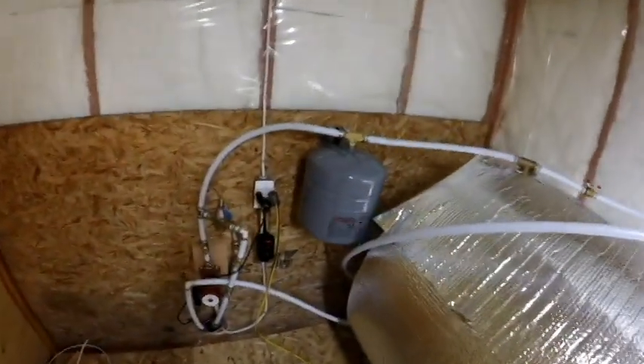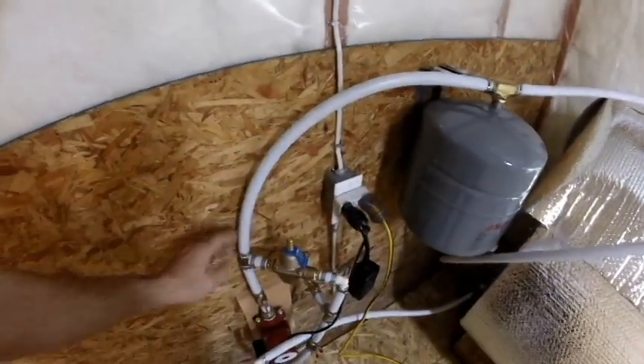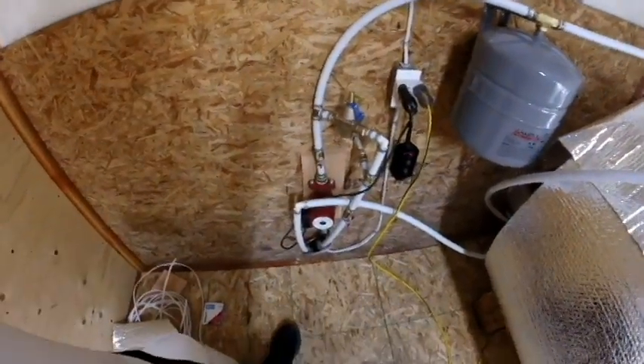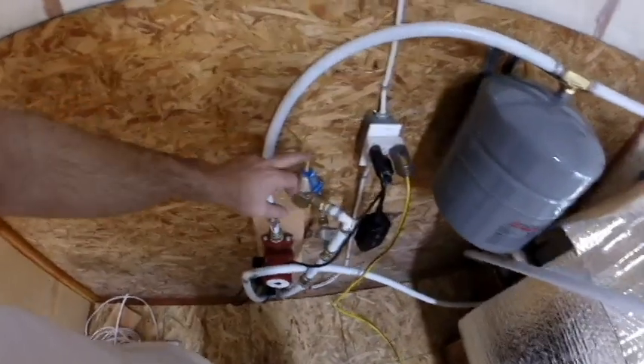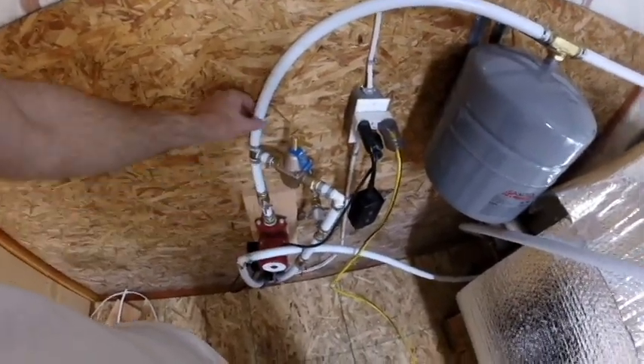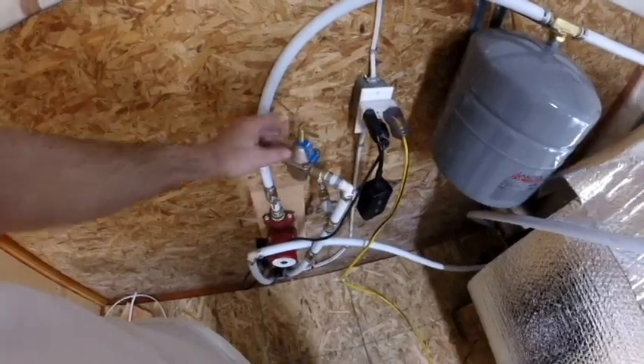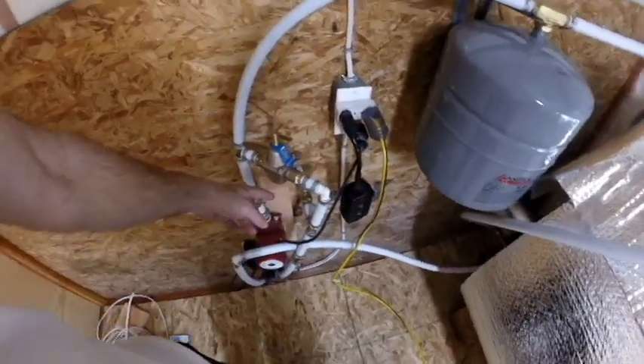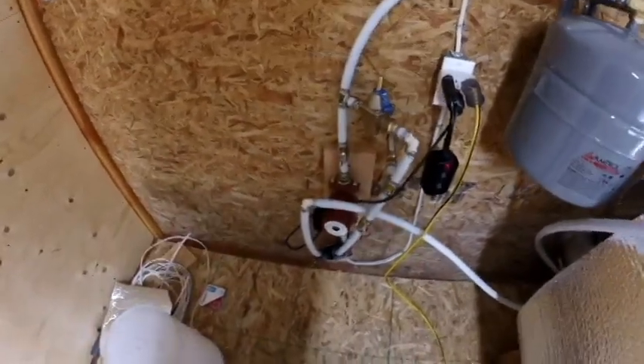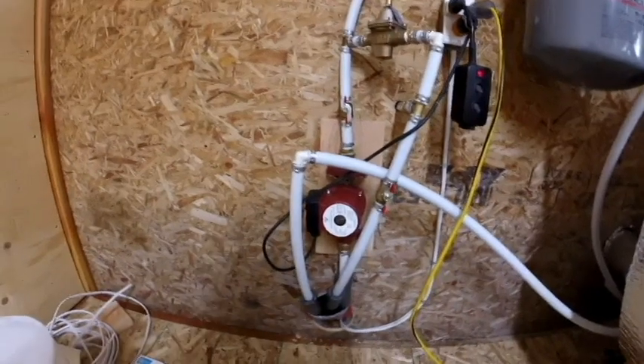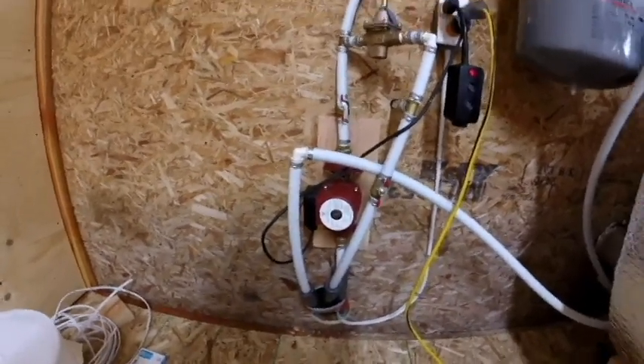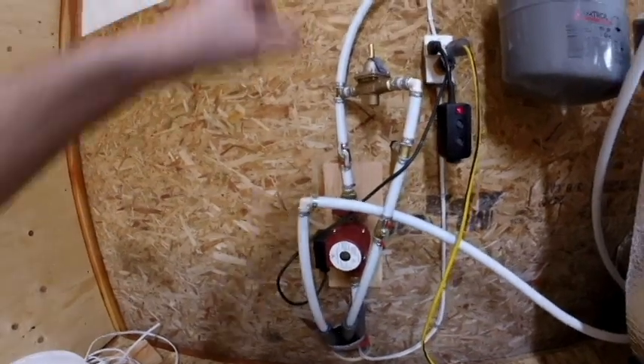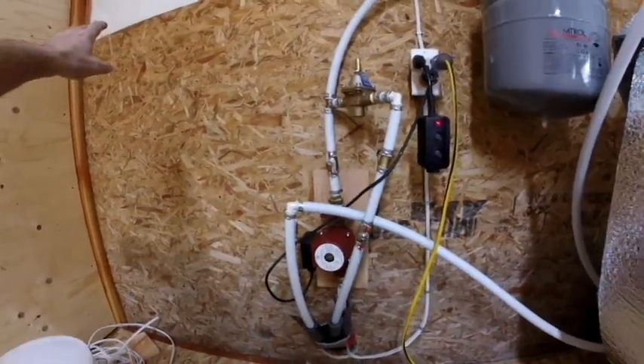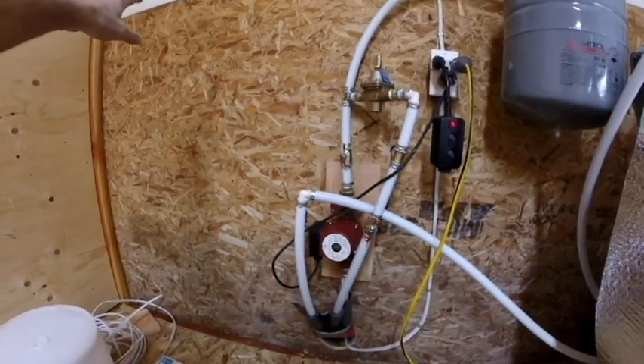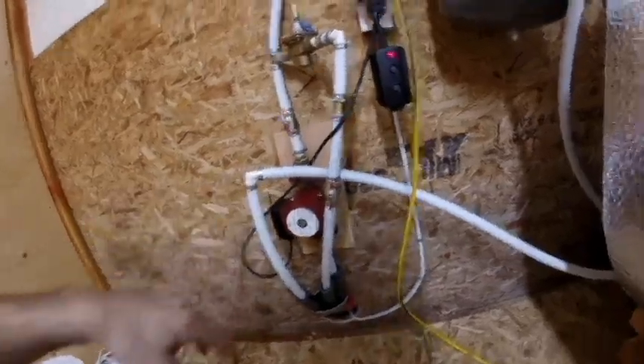The way I have this system here, I have the lines going in and out of the house. I also have water coming out from my house to fill the system, so it's on an autofill valve. So anytime the system needs water, minimum 15 psi, this will introduce more water into it. And also run an outside tap off that system. There I have a second 3-speed pump. This pump here is responsible for pushing the water in and out of the house. The water goes in through the pump. 100 feet of line goes to the house, heats through the water heat exchanger in the house, and then comes back out the return line here, which then returns the remainder of the hot water back to the bottom of the storage tank.